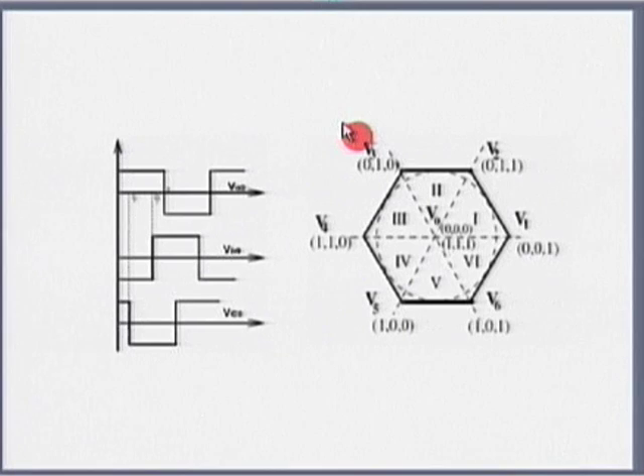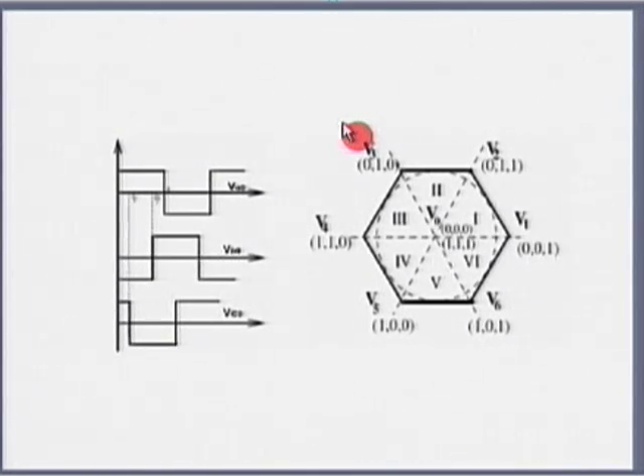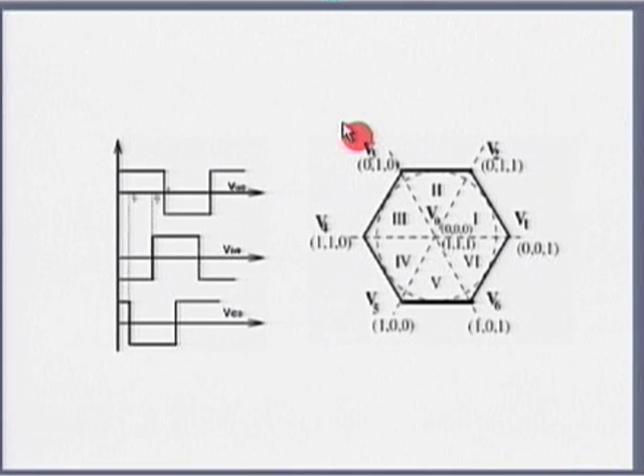The most common PWM strategy is the sinusoidal PWM technique, wherein there are 3 sinusoids displaced in time by 120 degrees. The frequency is equal to 50 hertz if I want a 50 hertz supply. It is compared with a high frequency triangular waveform. The frequency of the triangular waveform determines the switching frequency and therefore the frequency of the predominant harmonic.